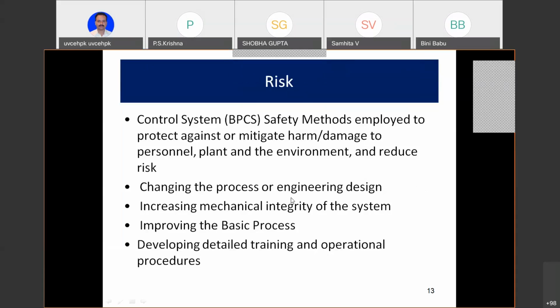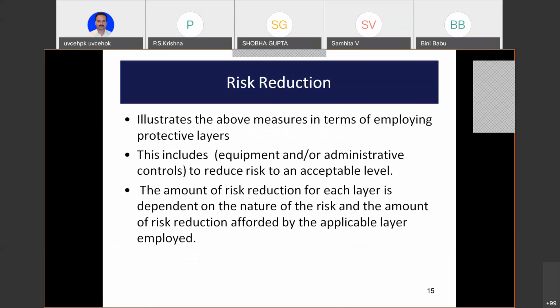Now, control system, BPCS, safety methods employed to protect against or mitigate harm, damage, etc. to personnel, plant, and environment, and reduce risk. Changing the process or engineering design. Risk, how do you reduce risk? BPCS, change the design, do a good mechanically integrated system. What did we do there? We brought that reactor and we said that it will fracture only at 55 bar. Then the process has also been tweaked by the process engineer, developing, training your operators so that they don't do the wrong things. I think we have to go fast.